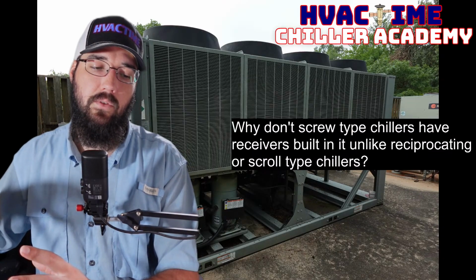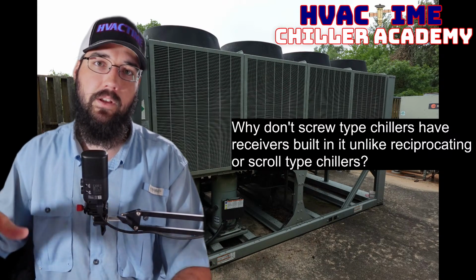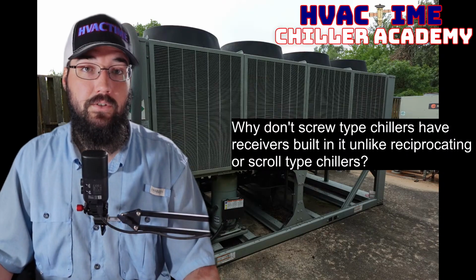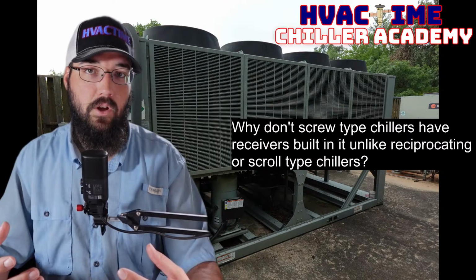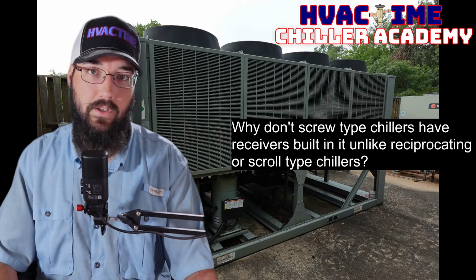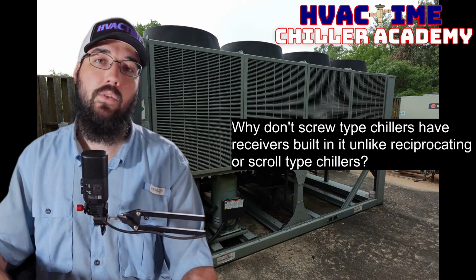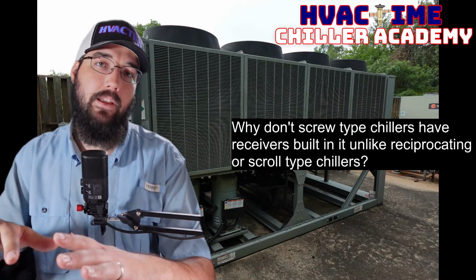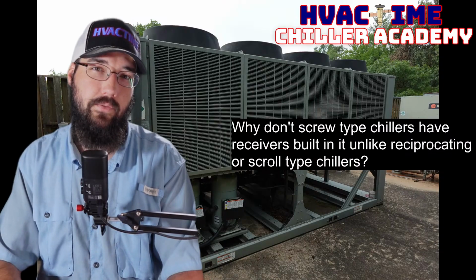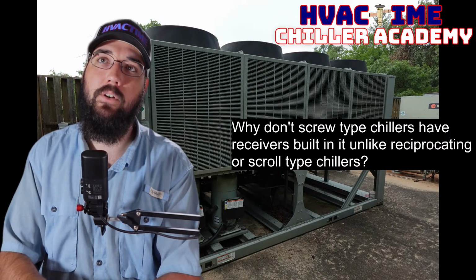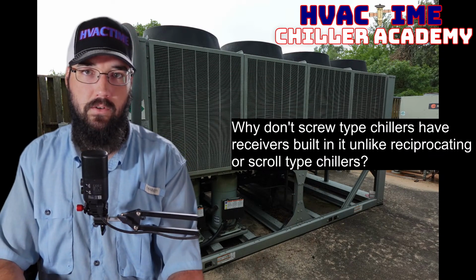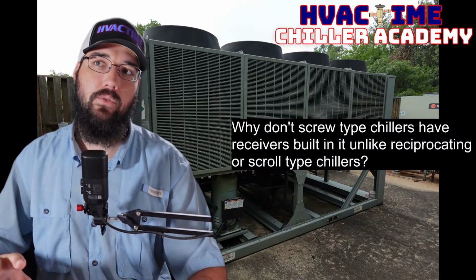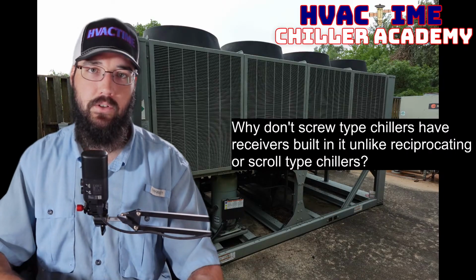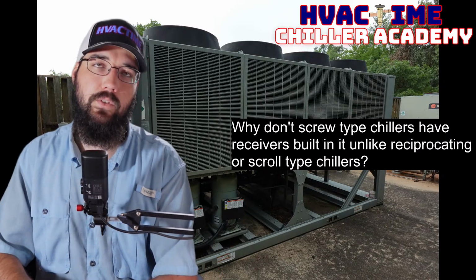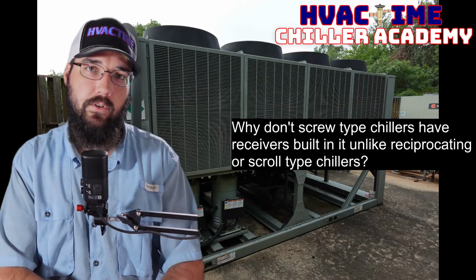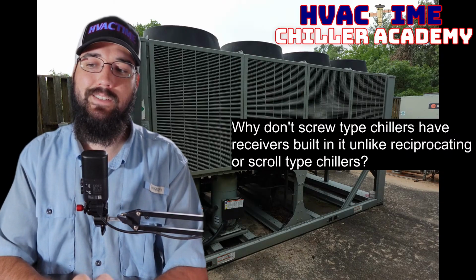So in those applications, that liquid line receiver becomes, call it, an expansion tank. If you're comfortable with hydronics terms, I would compare it to an expansion tank, where it helps us maintain pressure and store additional water, if you will, for the loop. If you're not comfortable with those either, it's just a type of reservoir, a refrigerant reservoir. Now, why don't standard machines, especially once you get into the screw and centrifugal world, use that? I would say it's because of the purpose they're built for. The loads tend to be far more stable and consistent.